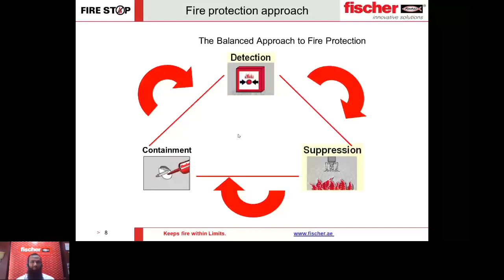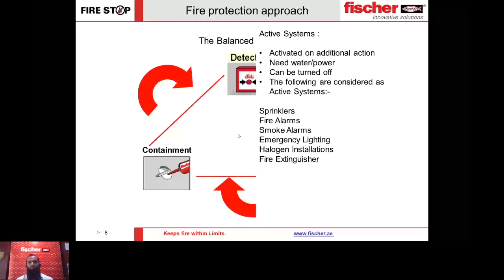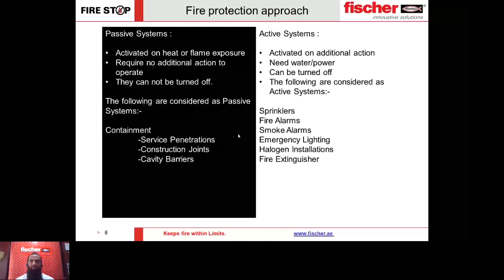Once fire is detected, we want suppression systems to activate to reduce the impact. However, there is a third pillar which most of us miss — containment, which is part of passive fire protection. The detection system and the sprinkler system are called active systems — these are plan A in fire protection. The moment there is fire, they get activated; they need water, power, and continuous maintenance, and can be turned off.